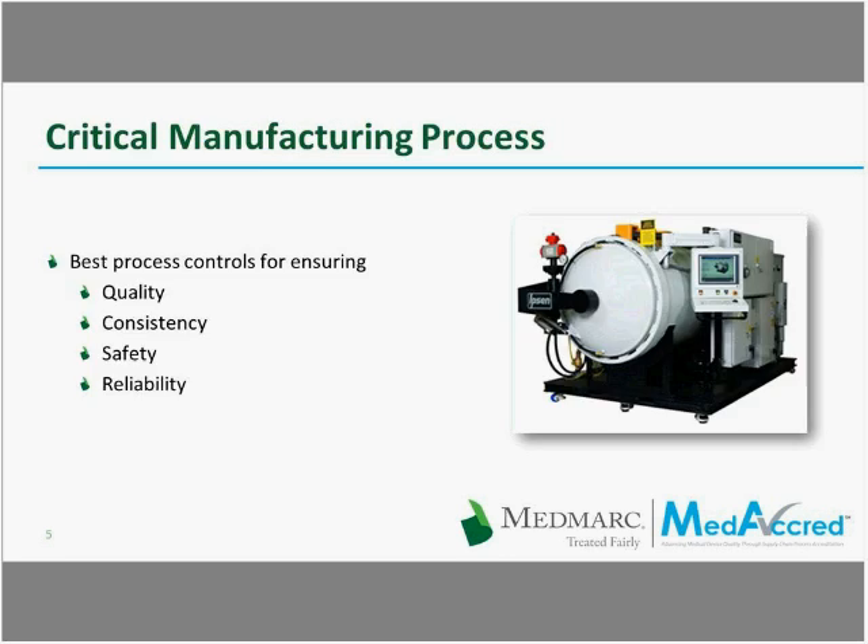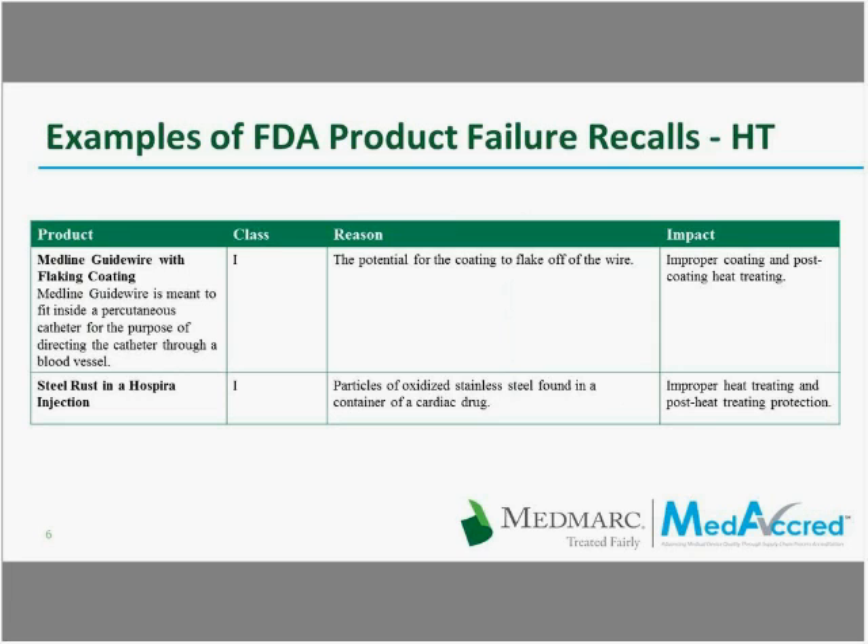You can see some examples of FDA product failure recalls nationwide due to causes including, but not always, heat treating. Medline guide wire with flaking coatings — the coating applied on the guide wire is many times post-coated heat treated, and the heat treating can affect this coating, which was flaking off. Also, steel rust in Hospira Injection, and particles of oxidized stainless steel found in a container of a cardiac drug — this is improper heat treating and post-heat treating protection. These are just two examples of how heat treating can be a culprit for failures.